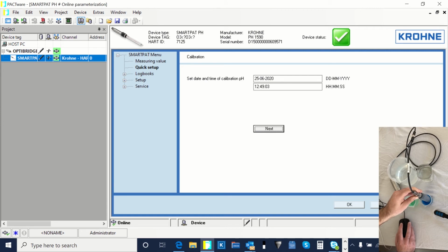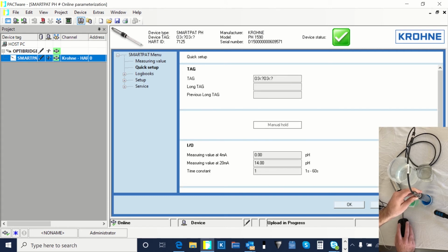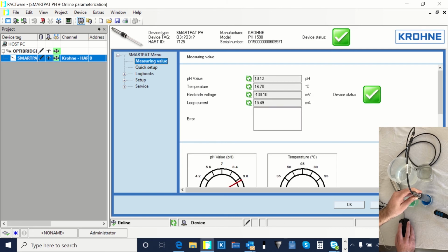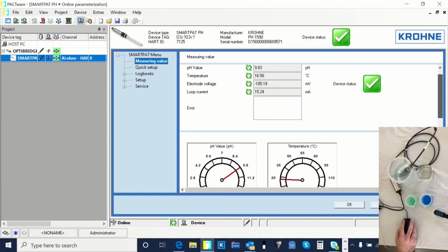And it'll put the date in, and when we've calibrated it, we'll keep a log of that. We're going to save value. And there we go, that's it. Basically all we need to do, we'll take that back, put it in our cleaning solution, which is just fresh water, and you can basically go and put the probe back in line.